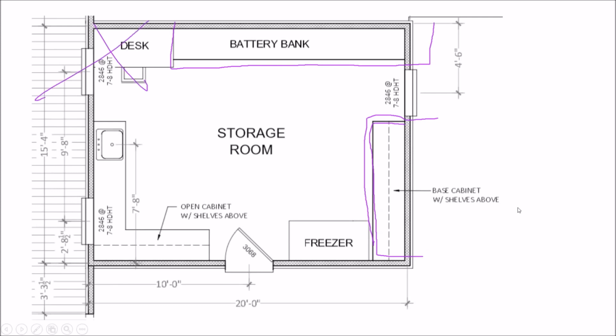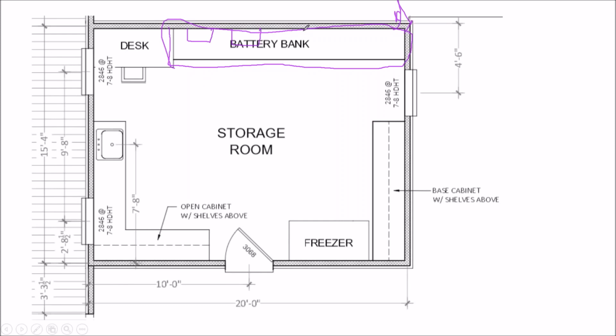This is kind of an architectural drawing. Say you're building a box and the battery bank is going into a completely enclosed, protected box that's off-gassed to the outside, and then you wanted to put additional electrical equipment and conduit runs in the space above the box. What you run into is you're only allowed a 6-inch gap between the faceplate of your electrical products and the furthest extended electrical device on the same vertical plane.